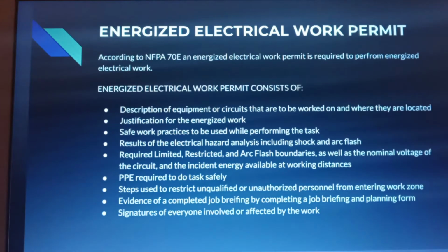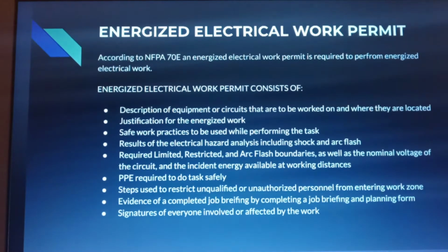All right, energized electrical work permit. We're going to get into what it is and what all is included in it. So according to the NFPA 70E, an energized electrical work permit is required to perform energized electrical work. So what the energized electrical work permit consists of is a description of the equipment or circuits that are to be worked on and where they are located. Justification for the energized work, as in why you need to work on it hot. And then the safe work practices to be used while performing the task.